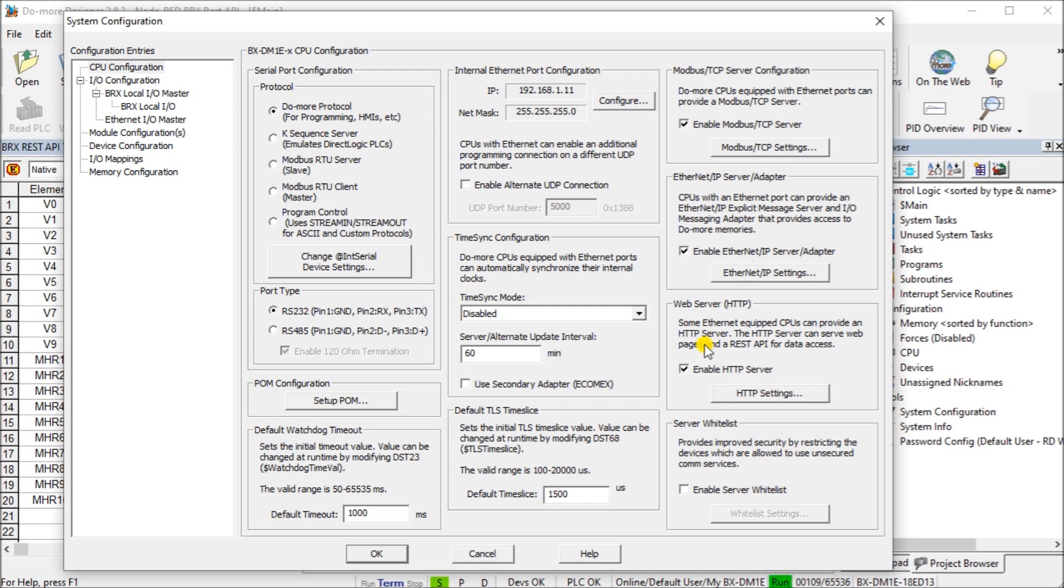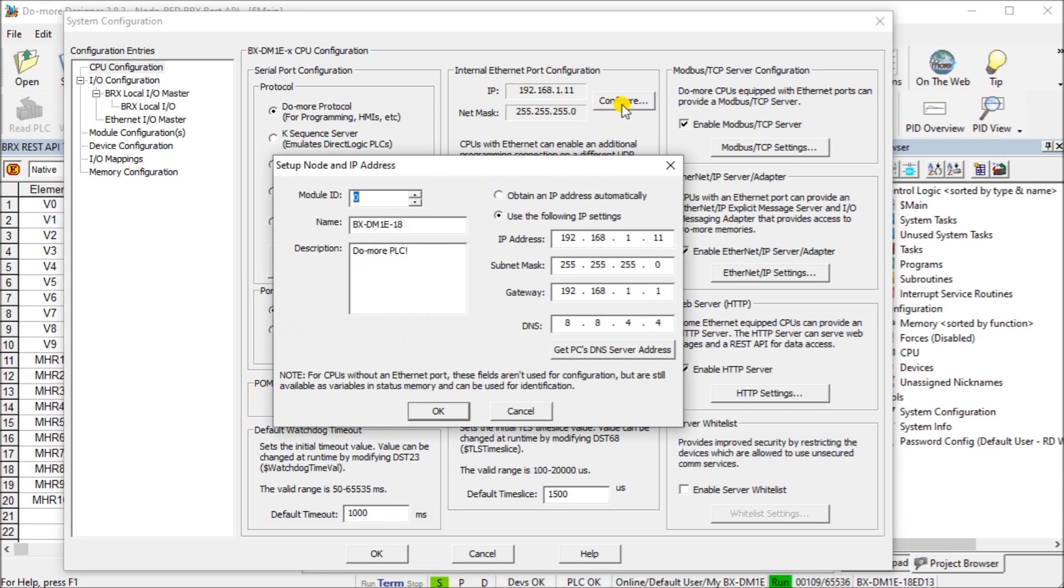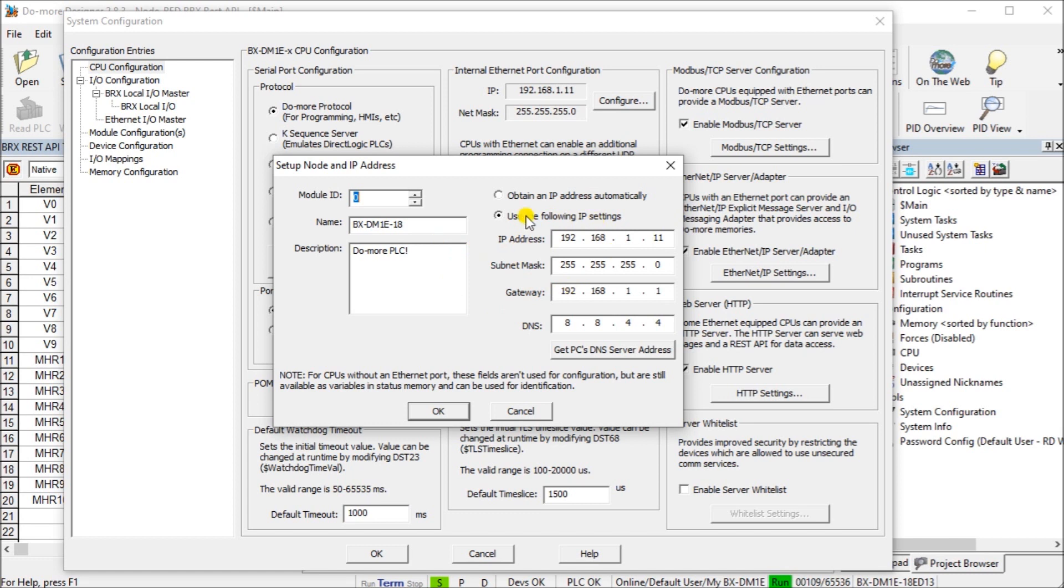We also should look at the IP address. In this particular case, my Do More controller has an IP address of 192.168.1.11. If we look at the configuration of that, you will see that we have it uses the following. We've set a static IP of that address. This is my subnet mask, my gateway and DNS. It's important to have a static IP in order to determine exactly where this controller is when we do our requesting of the information using the REST API.